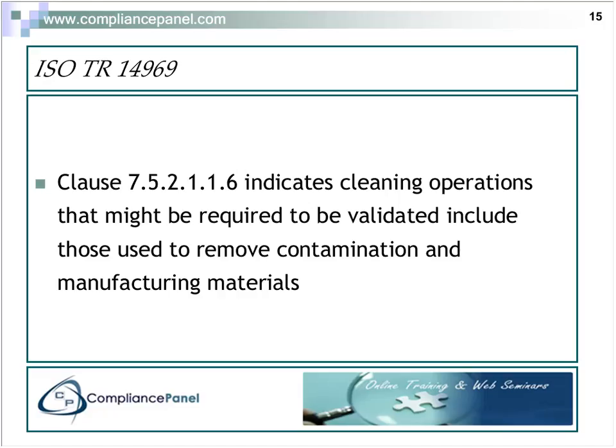Now, the numbering of this does follow the numbering of 13485. In fact, this document does include the entire text of 13485. So if you had your choice of which one to buy, I would buy 14969 and not buy 13485, because all of the requirements from 13485 are located inside 14969, right adjacent to the discussion of each of those requirements.